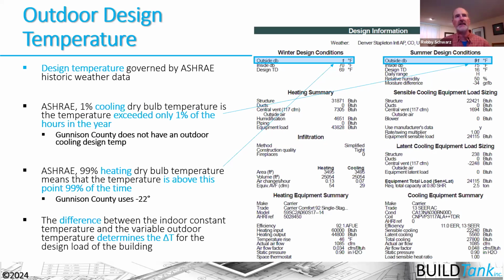Now, the design conditions that were entered into this particular HVAC design, or Manual J, were based on Denver. So we see that -1 and 91. I believe it's gone up to 93 now in Denver there. But we see that, again, it's dependent on the climate location that you're located in, where you're going to get those design conditions here.